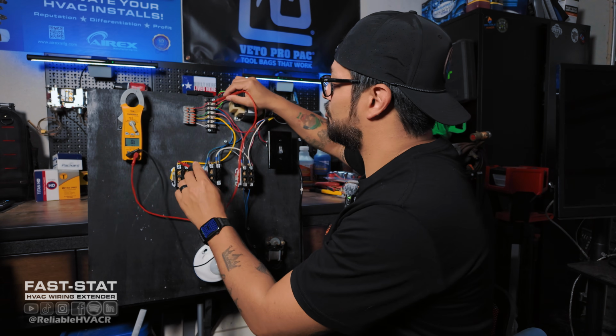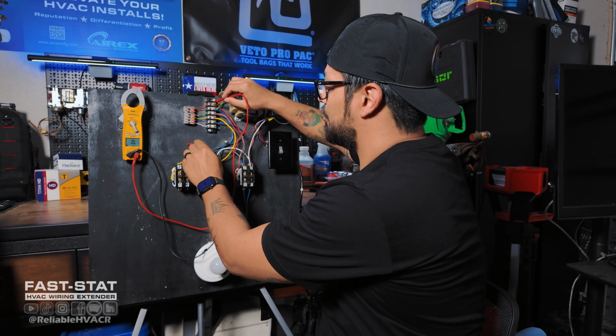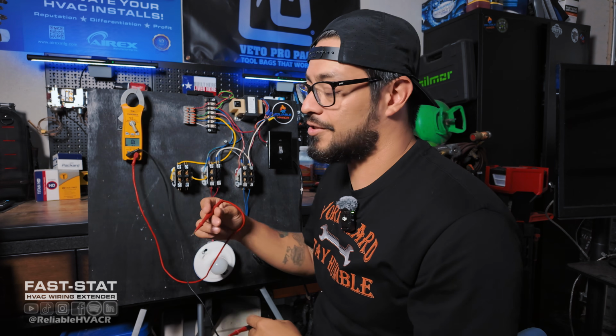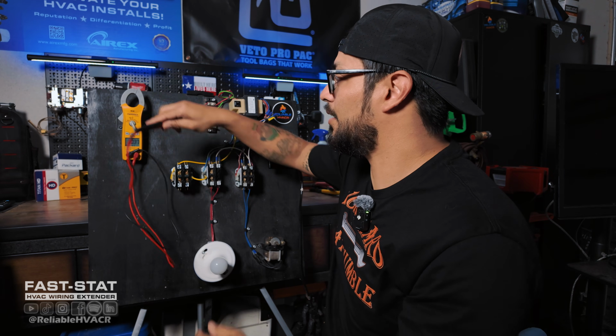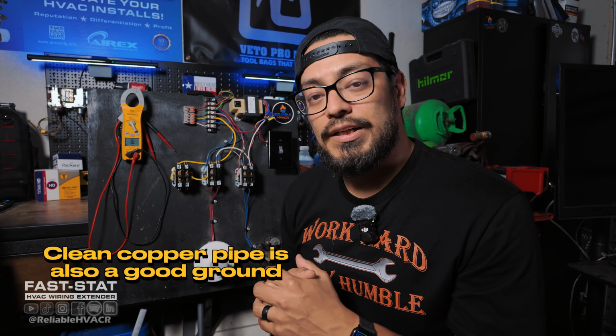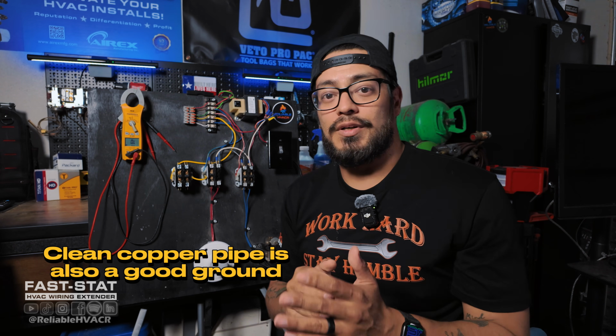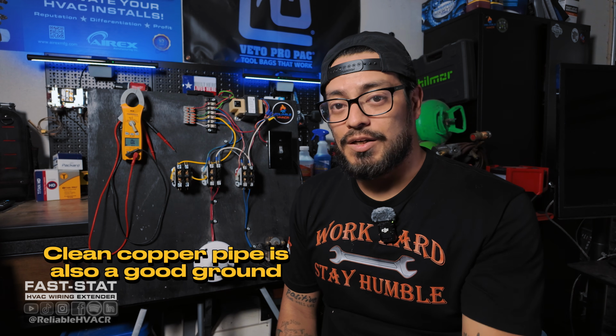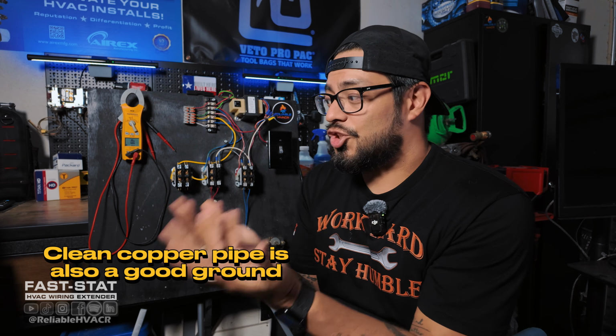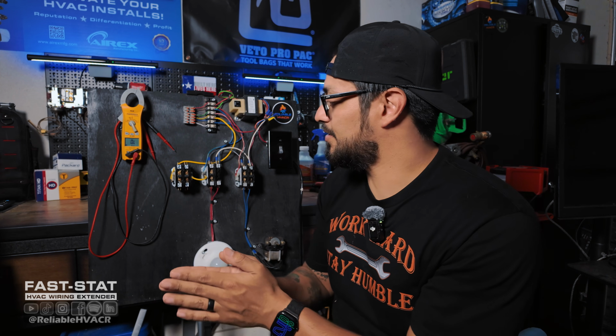So then you're going to go to each one and you're going to start the wire itself. You're going to start checking to any good metal. Like I said, make sure that it is a ground by checking it. And then check each one to that metal and make sure it's not touching. It can be continuity. If you guys are checking resistance, you want OL or some higher form of resistance.